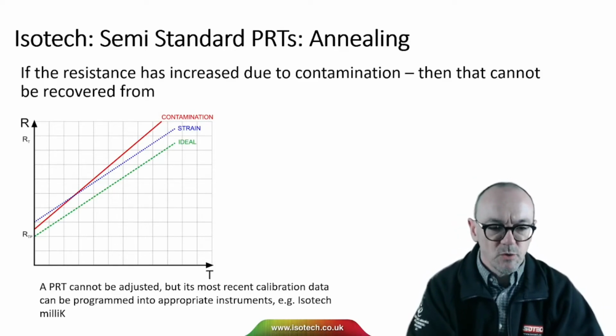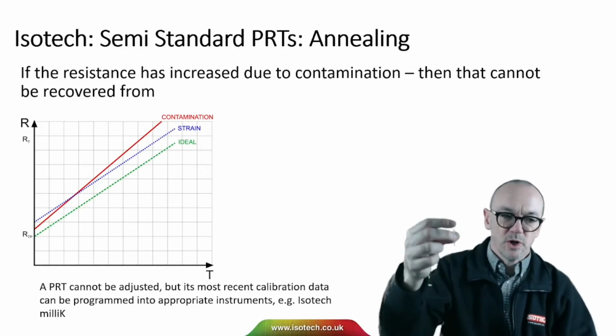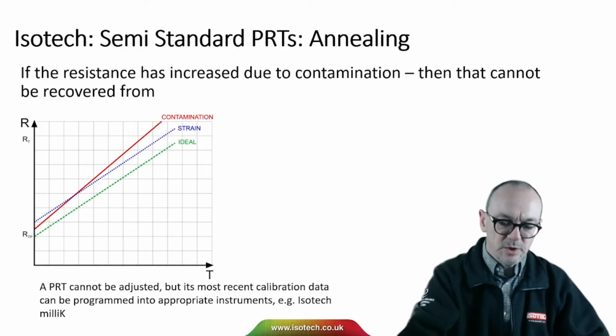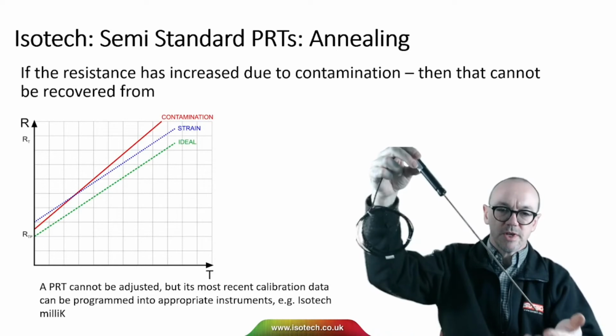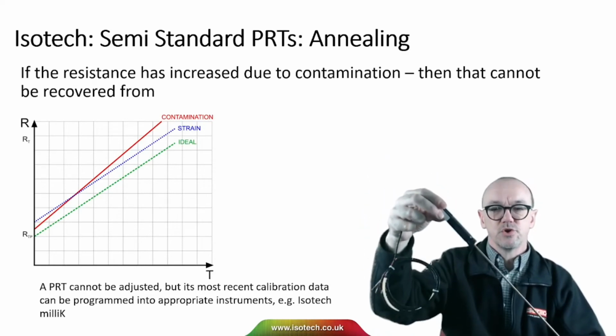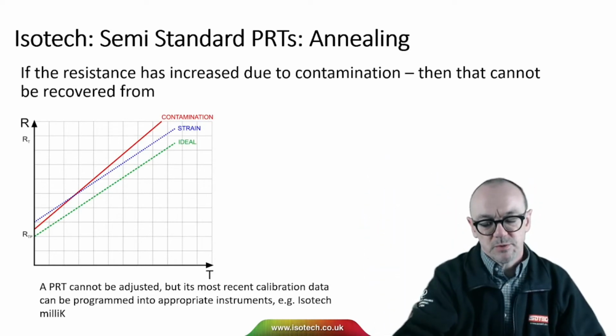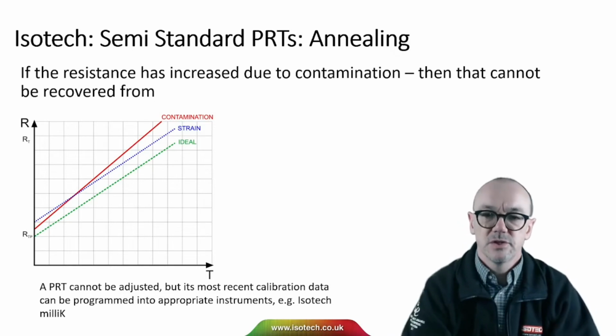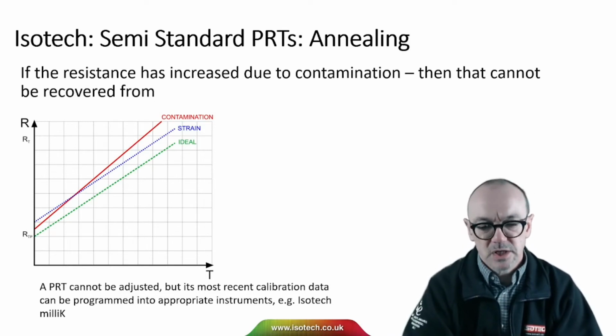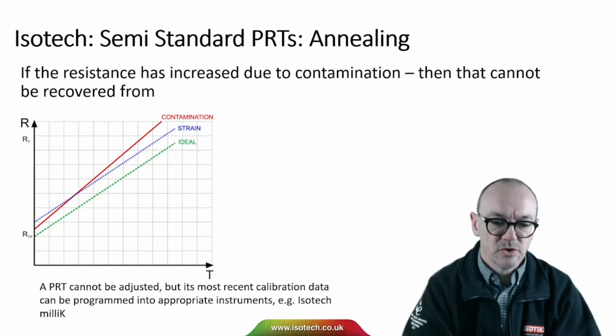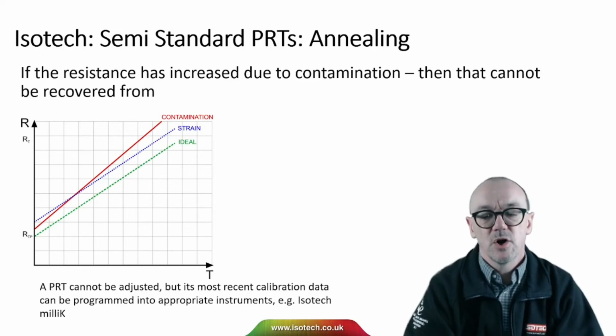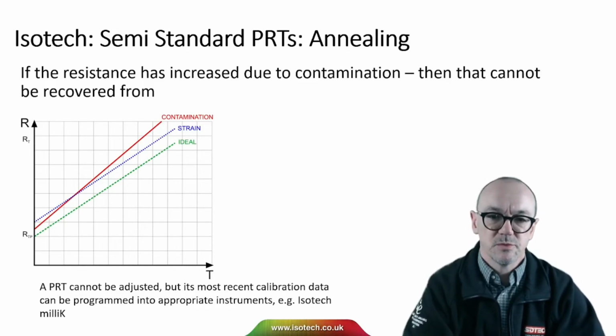And the PRT, if you remember, it's just this simple coil of platinum wire sealed into a thermometer. And once that thermometer is made, we can't adjust the PRT, but the instrument that it's connected to can be updated with the latest information from the thermometer's calibration. And you can program in perhaps the water triple point and the coefficients that relate to the relationship between resistance and temperature. So a PRT can't be adjusted, but the information from it can be programmed into a suitable instrument.